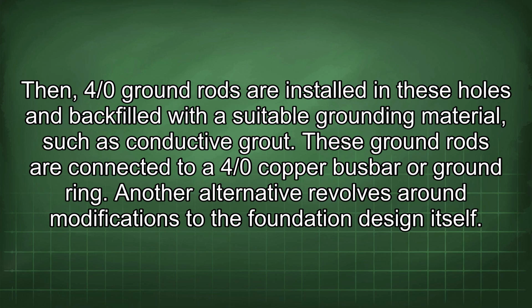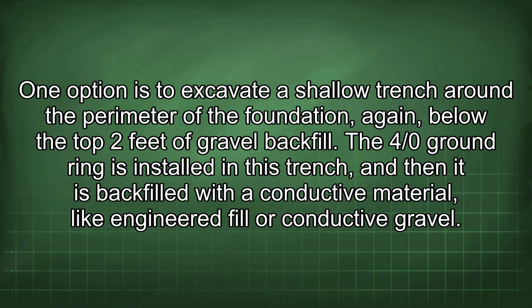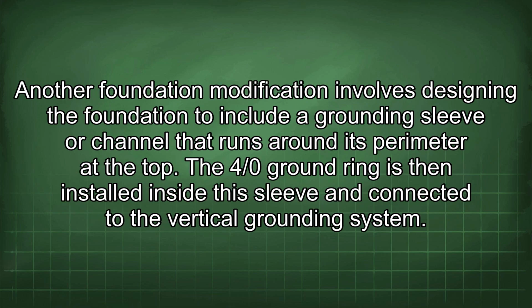Another alternative revolves around modifications to the foundation design itself. One option is to excavate a shallow trench around the perimeter of the foundation, again below the top 2 feet of gravel backfill. The 4/0 ground ring is installed in this trench, and then it is backfilled with a conductive material, like engineered fill or conductive gravel. Another foundation modification involves designing the foundation to include a grounding sleeve or channel that runs around its perimeter at the top. The 4/0 ground ring is then installed inside the sleeve and connected to the vertical grounding system.